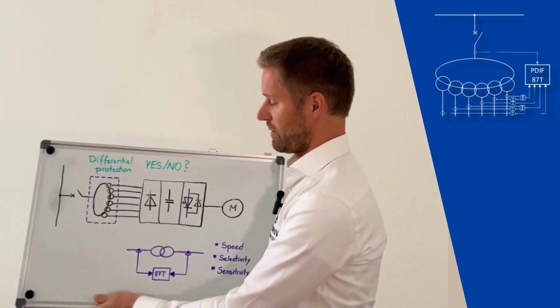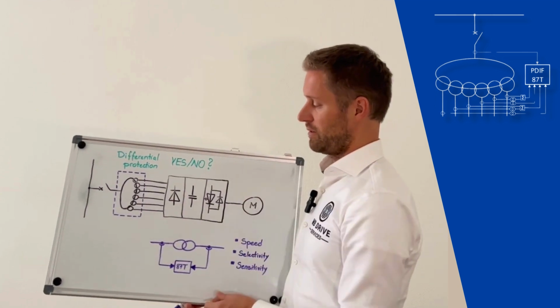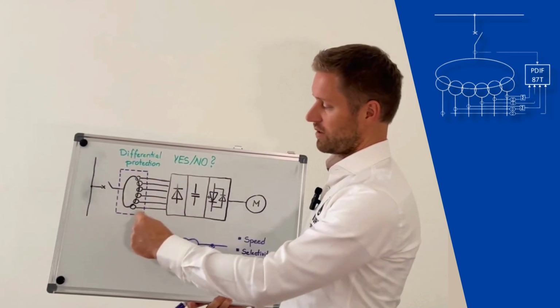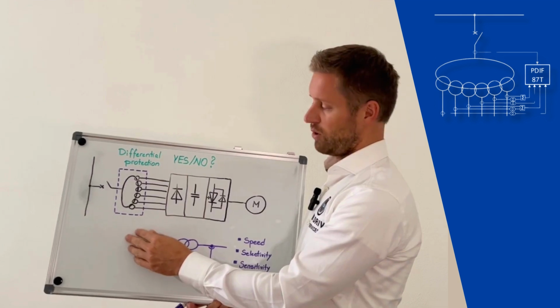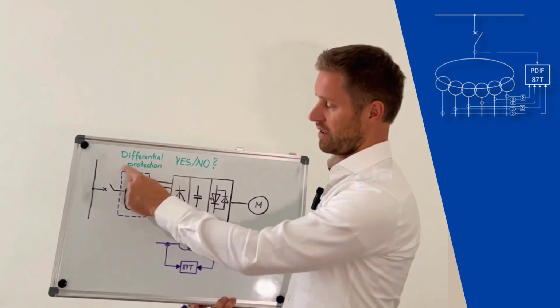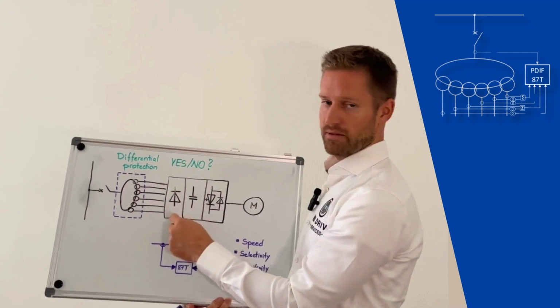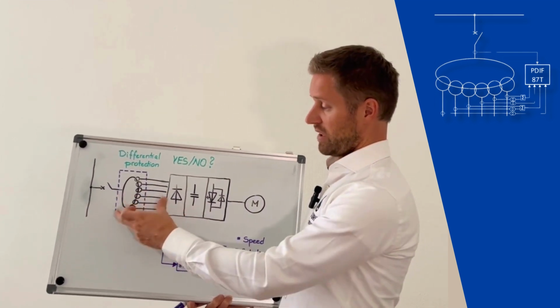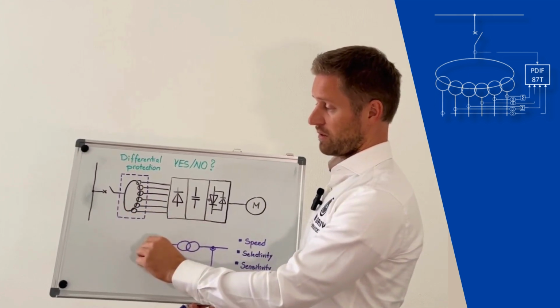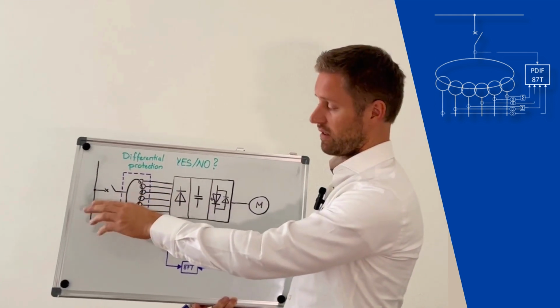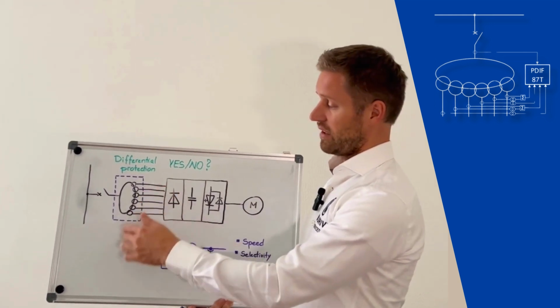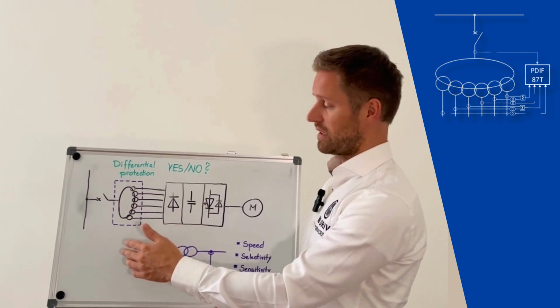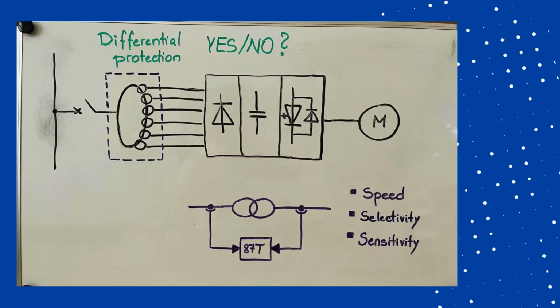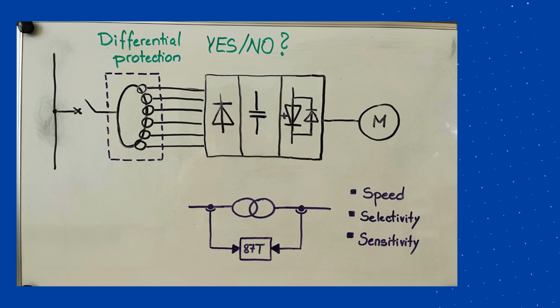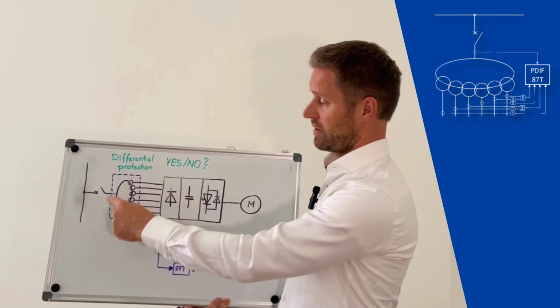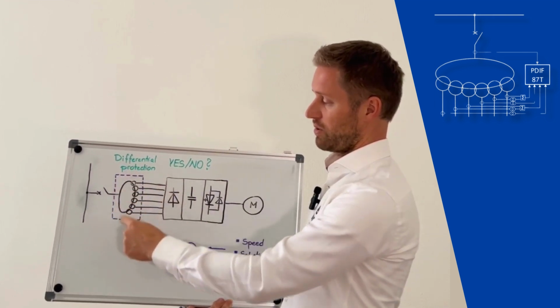For that purpose, I have prepared a small sketch with a medium voltage drive system. We can see the input transformer in the dotted box. As you probably know, medium voltage drives often require a multi-winding transformer because they have a multi-pulse rectifier, especially if it's a diode rectifier, and the combination of the two shall eliminate certain harmonics from the spectrum, so that the harmonics injected into the grid are low, within the limits of the standards, and the necessity for a harmonic filter can be eliminated. And then the question is whether the differential protection can and shall be applied on such a multi-winding transformer or not.